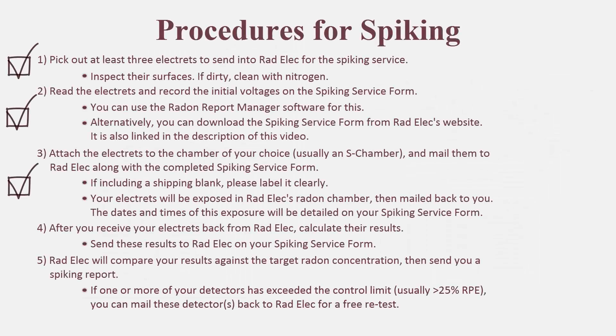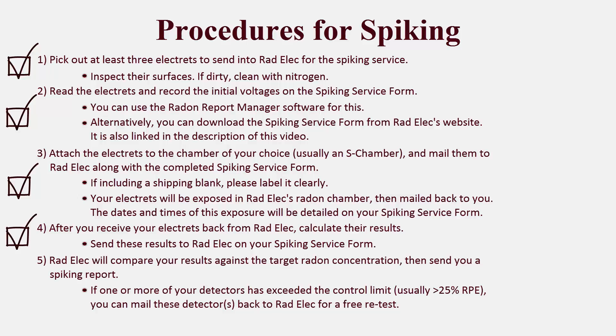That pretty much brings us to the end of the spiking procedures. After you receive your detectors back from the chamber, calculate their results and send your completed spiking service form with the radon concentrations back to Rad Elec. You can use the Radon Report Manager for this, or calculate them on your own — just make sure your gamma and elevation are set to the values defined by the radon chamber. The fifth and final step involves receiving your final spiking service report from Rad Elec, entering the target radon concentration into the software, and taking a look at your relative percent errors.